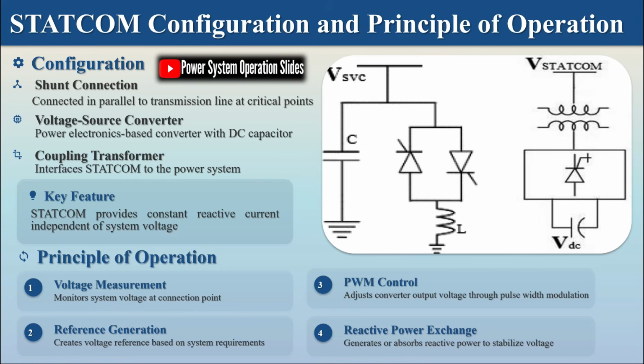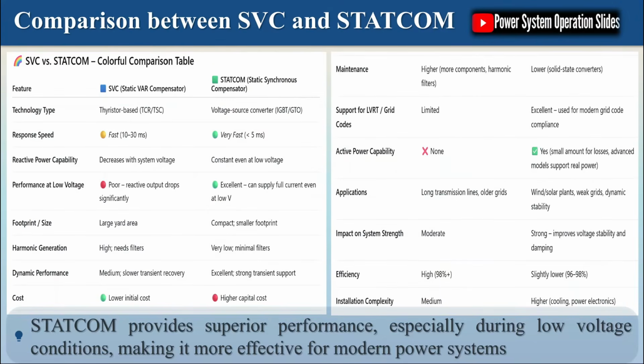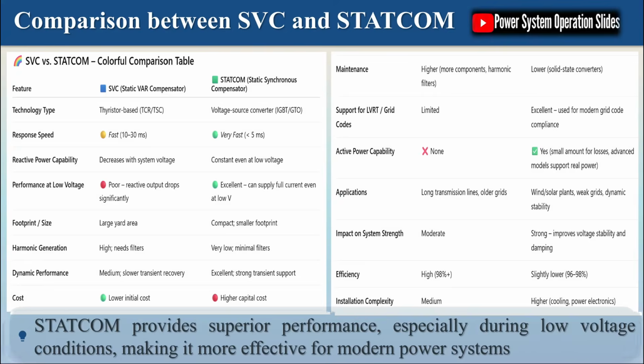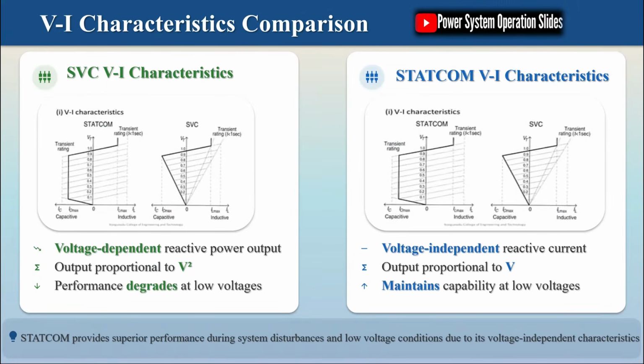However, these technical advantages come at a cost. STATCOMs are generally more expensive than SVCs due to the more complex power electronics required for the VSC topology. The initial capital cost of a STATCOM can be significantly higher than that of an equivalent SVC, which may be a determining factor in some applications. Additionally, the control systems for STATCOMs are more complex, potentially requiring more sophisticated maintenance and technical expertise.